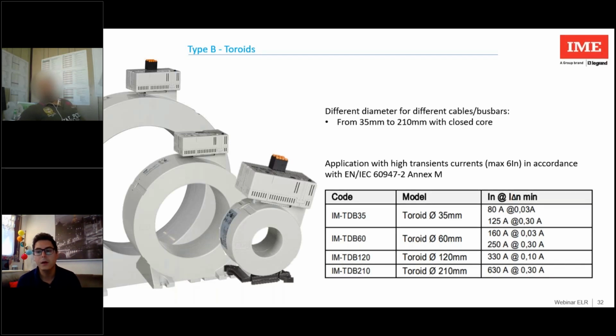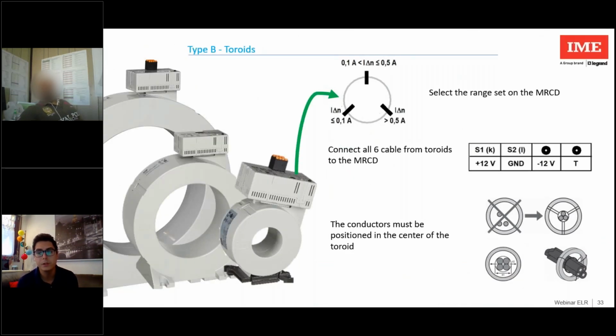Not only that. In fact, on the upper part, there is a 3-position rotary switch in which we have to set the same differential current value you set on the MRCD. The connection between the toroid and the differential relay takes place via 6 wires. 2 will be for the AC core, 2 for the DC core, and 2 for powering the hardware component present on the toroid, because it is also an active part for detecting the fault. The central rules for the conductor remain the same as for the AC toroids.